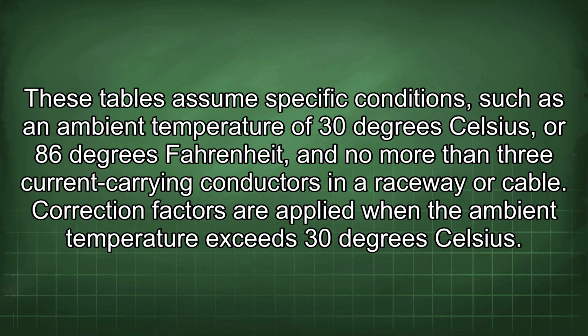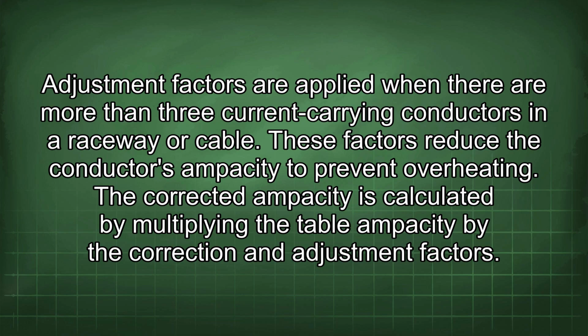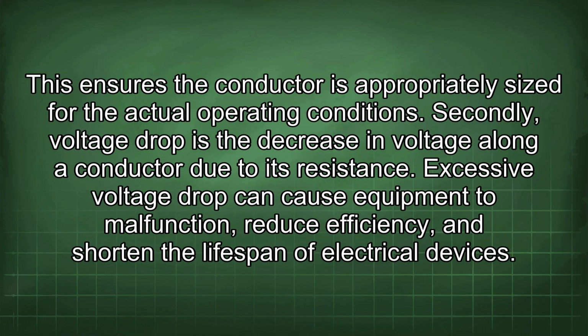Correction factors are applied when the ambient temperature exceeds 30 degrees Celsius. Adjustment factors are applied when there are more than 3 current-carrying conductors in a raceway or cable. These factors reduce the conductor's ampacity to prevent overheating. The corrected ampacity is calculated by multiplying the table ampacity by the correction and adjustment factors. This ensures the conductor is appropriately sized for the actual operating conditions.